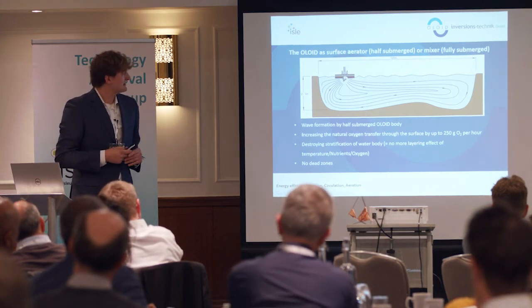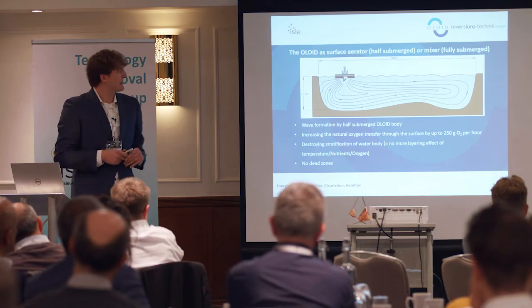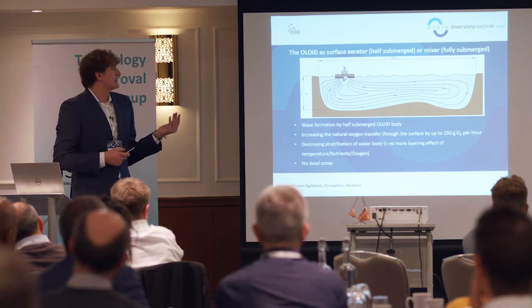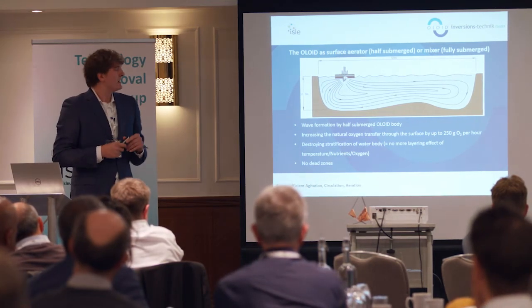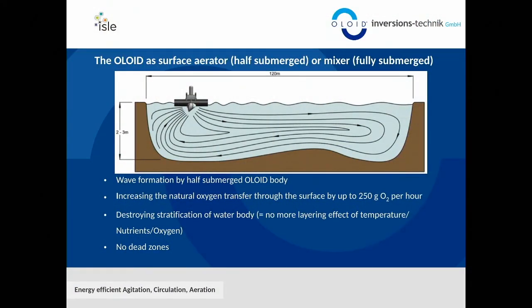In some applications where the required aeration level is not so high, the Oloid can also introduce oxygen itself. This depends on how deep the Oloid is submerged. If submerged completely, it acts only as a mixer. If positioned at the surface, it generates waves, which increase the surface area, allowing oxygen to naturally enter the water. Mechanically, the Oloid moving at the surface also sucks oxygen inside.